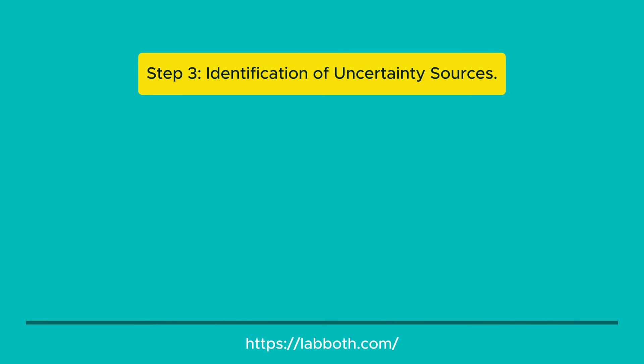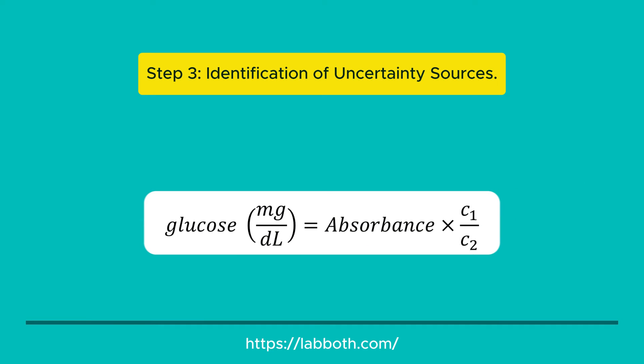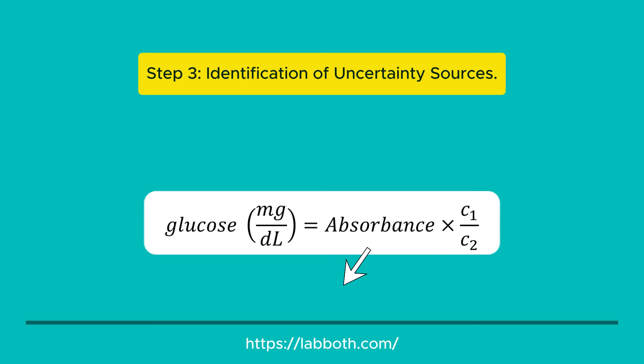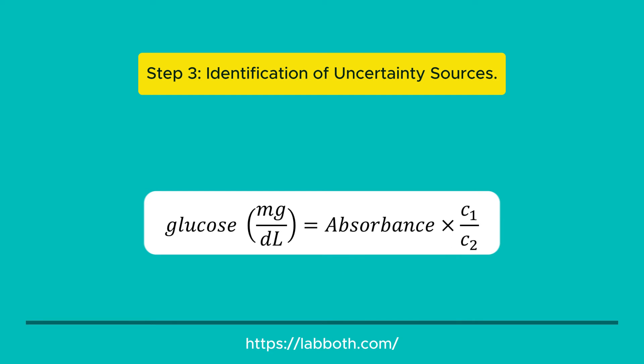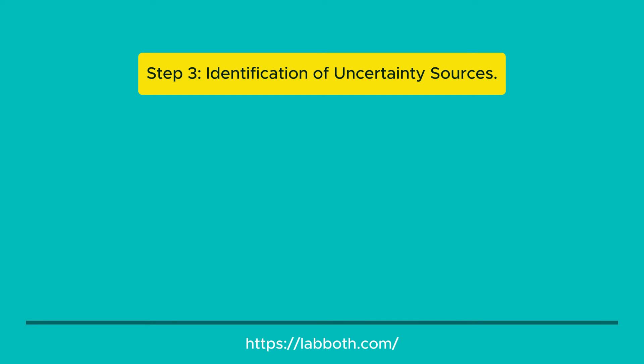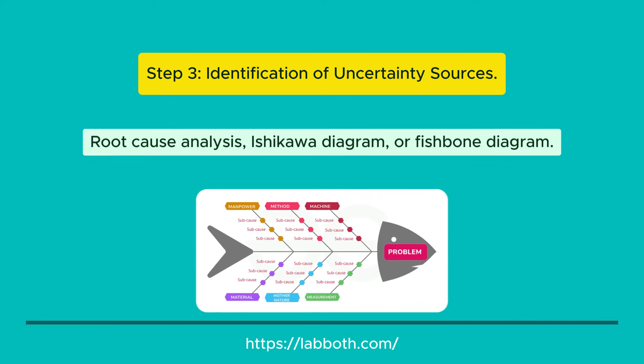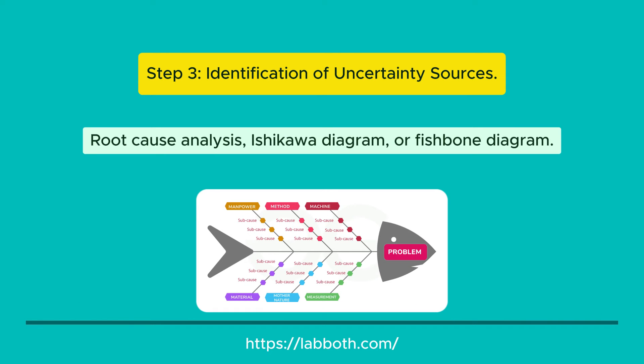Step 3: Identification of Uncertainty Sources. Once you have the measurement model, proceed to identify the sources of uncertainty. Start by identifying the input magnitudes of your measurement model, as each input magnitude is a source of uncertainty. These input magnitudes may in turn have secondary sources. To properly identify sources of uncertainty, I recommend conducting a root cause analysis using an Ishikawa diagram, or fishbone diagram. This diagram allows you to identify and organize the sources of uncertainty in the measurement system.